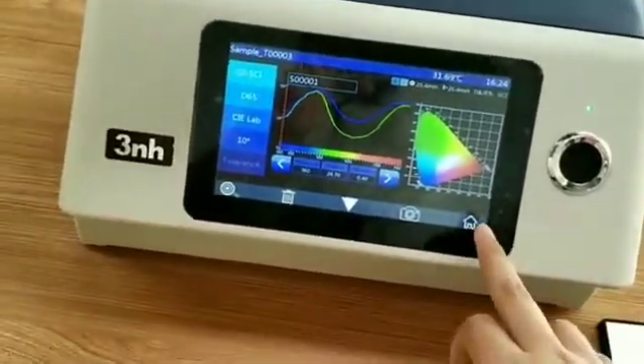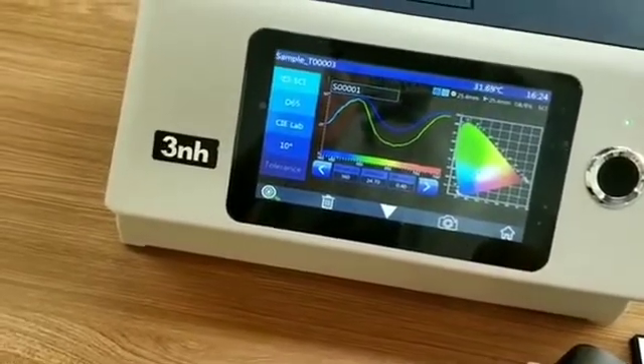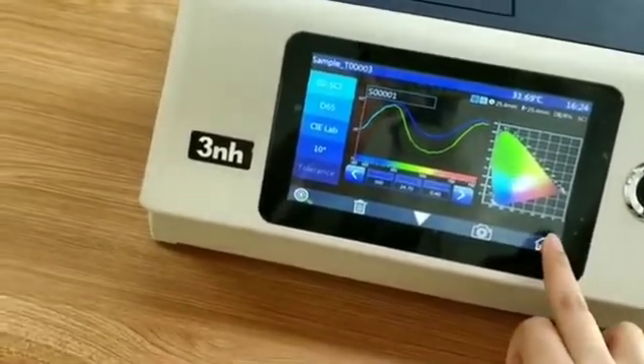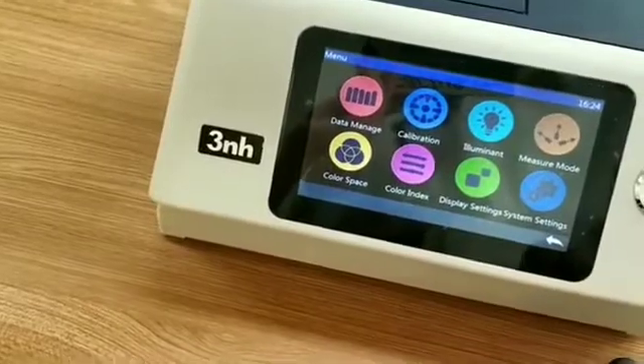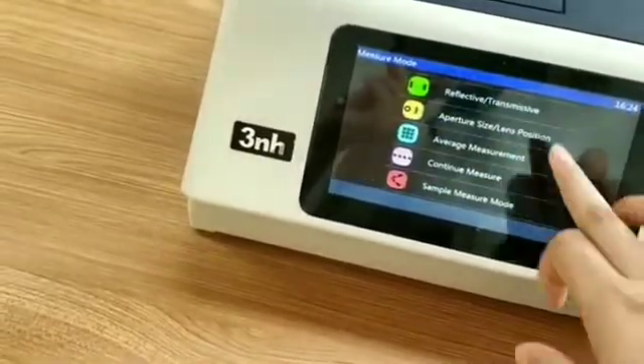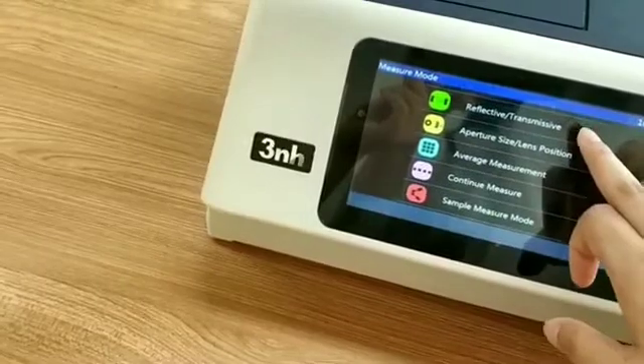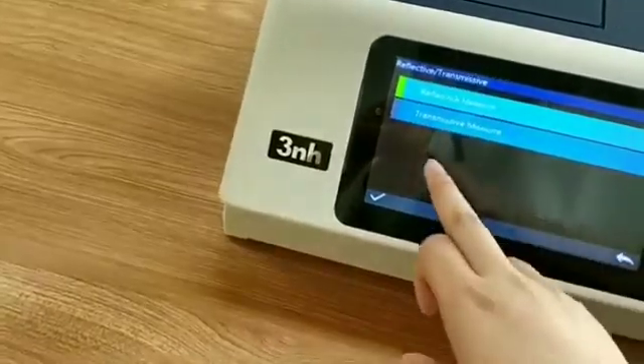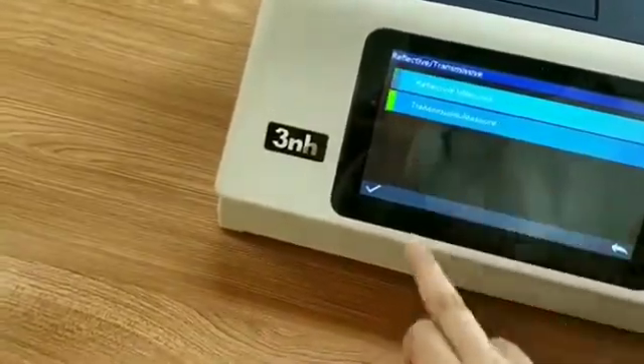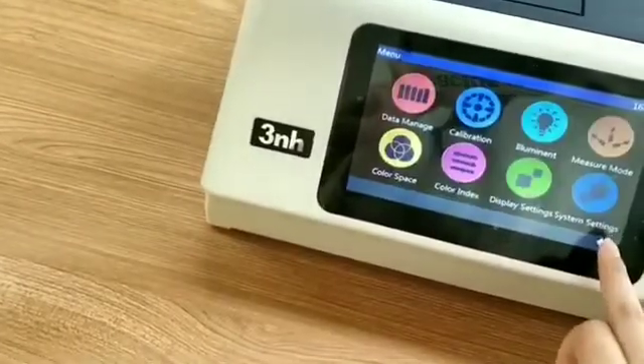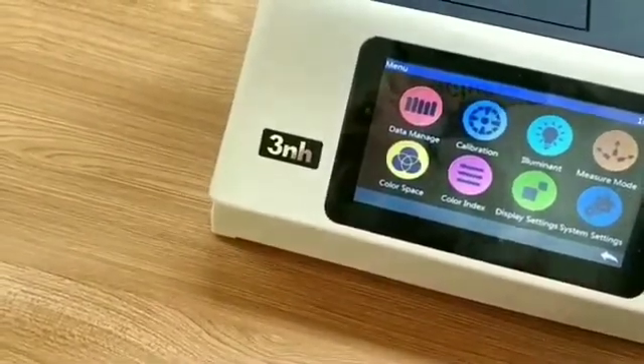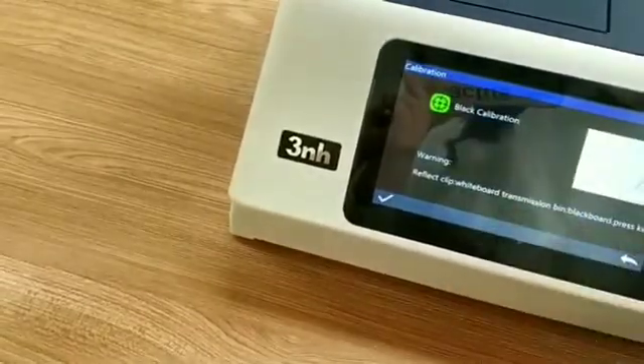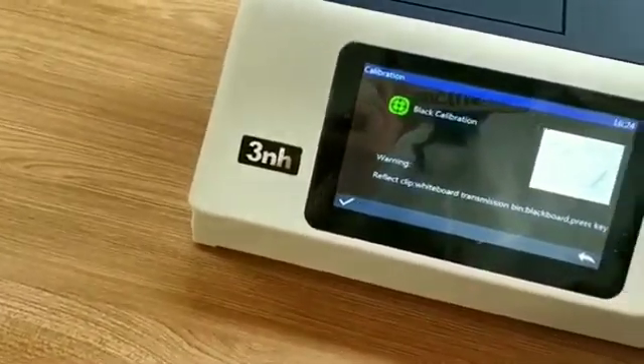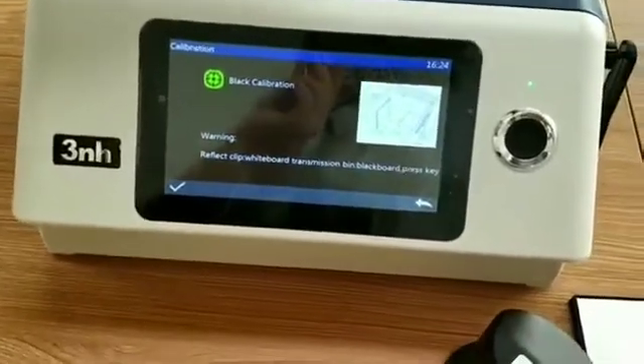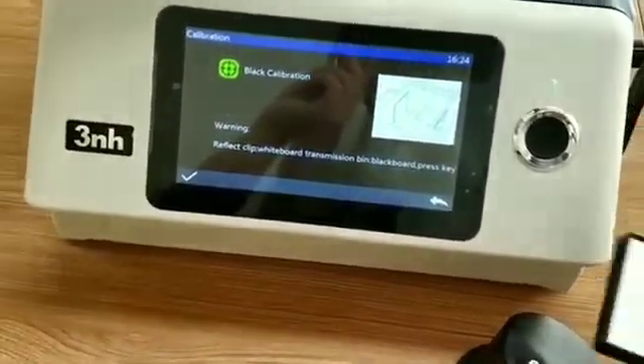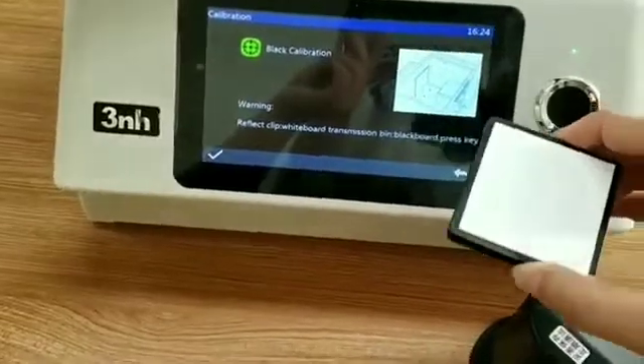Then we test the transmissive materials. Enter the main menu. Click the measure mode. Click reflective or transmissive. Select transmissive measure. We need to do the calibration again. When testing the transmissive material, the reflective white plate should be attached to the reflective aperture.